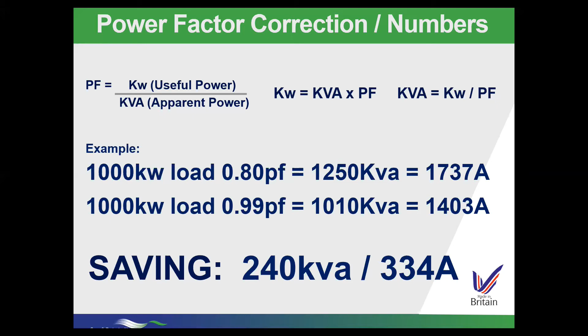And as you can see, there's massive reductions in demand. So if your organization is potentially overloaded and the main supply keeps tripping, then this is a really good application to stop that from happening. Or equally, if you want to expand and you've not really got enough power, again, a good solution to look at is power factor correction. Next slide, please, Chris.